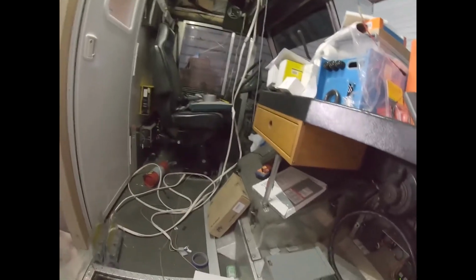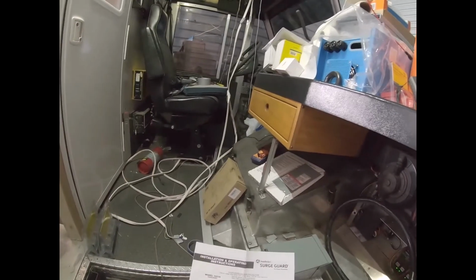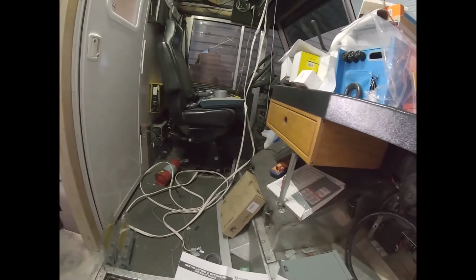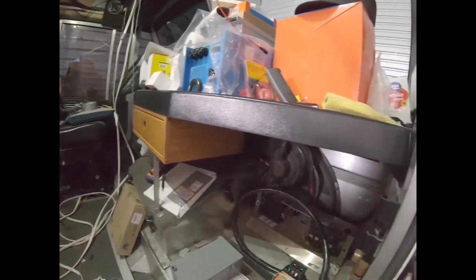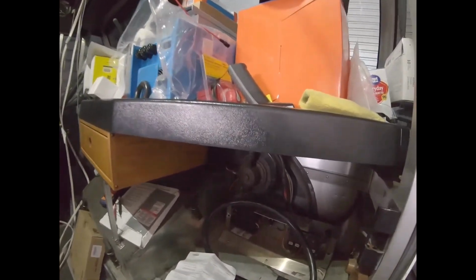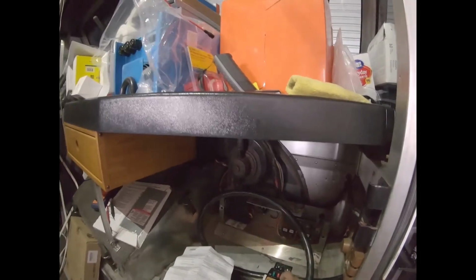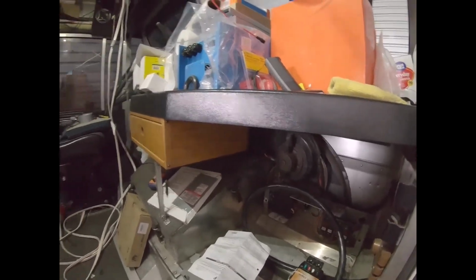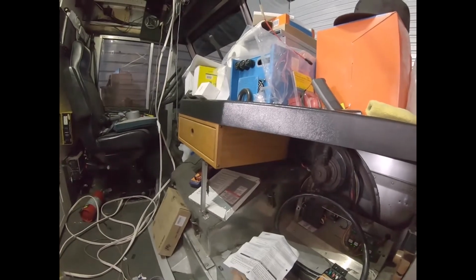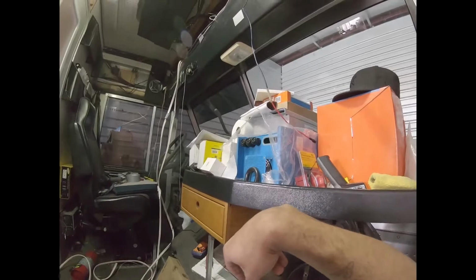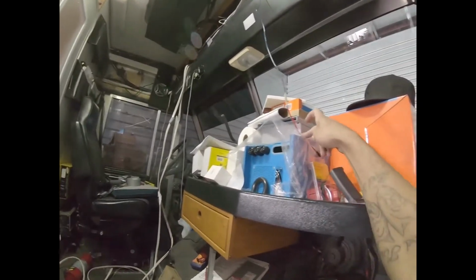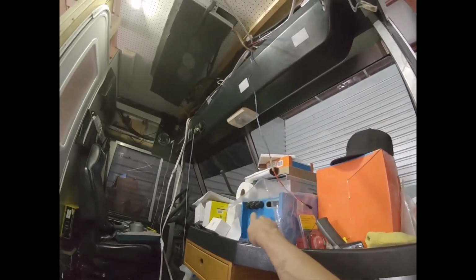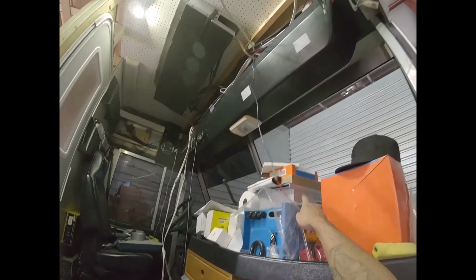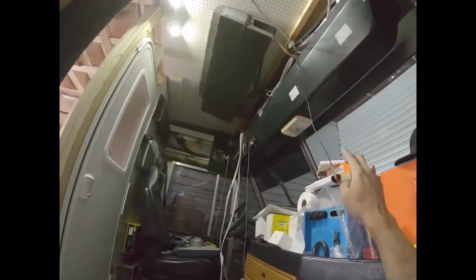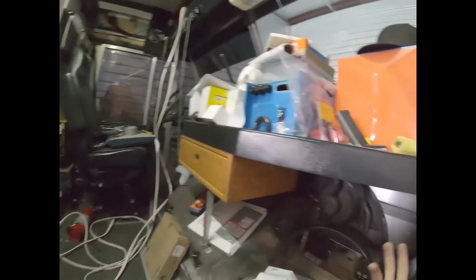I just got finished reading through the instructions, just to kind of verify which one is supposed to actually go first. So line power in goes to the surge guard first, then load out to the circuit breaker, and then from the circuit breaker to the inverter here, and then from the inverter to the distribution panel for the outlets, for the TV outlet and stuff.